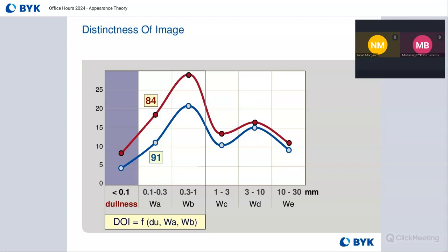Yeah, so piggybacking off of what Ray said, there's no standard essentially for measuring this type of appearance with the WaveScan. But what you're really looking for is how you want your finished product to look, and then creating pass-fail tolerances using equations that take into account the structure spectrum with all those different scales from the dullness to the WE, in order to make your process more likely to have that end result every time.